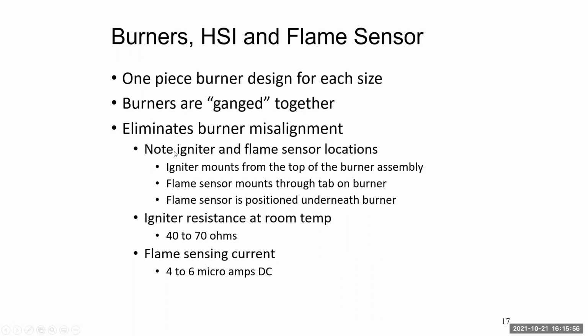Yeah, burners are ganged together, which eliminates your misalignments. Here it is again, 40 to 70 ohms at room temperature on your igniter, 4 to 6 microamps on your flame sensors. With that being said, don't just assume that a unit firing up and shutting right back down 2, 3, 4 seconds later has a bad flame sensor.